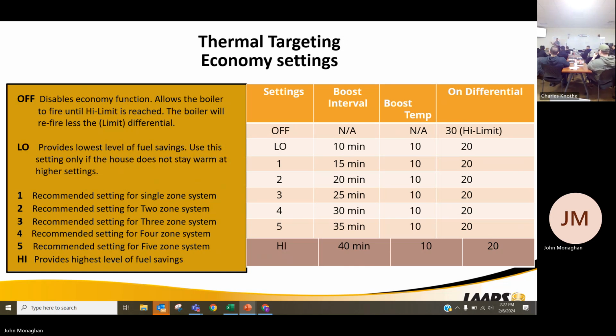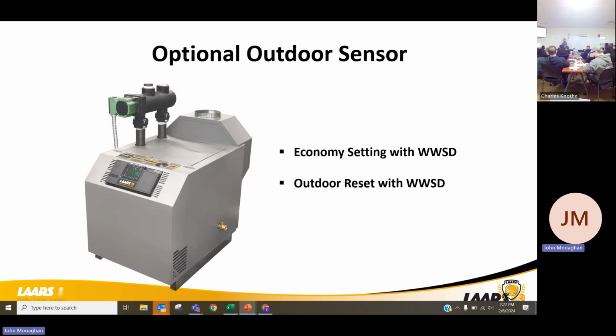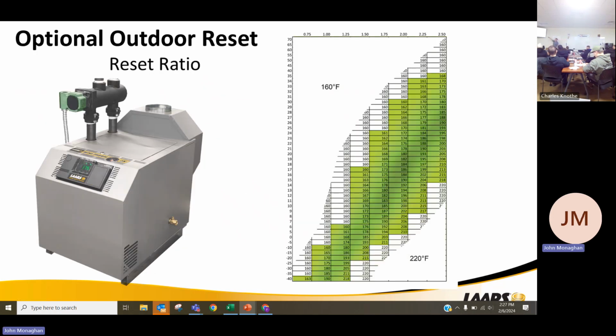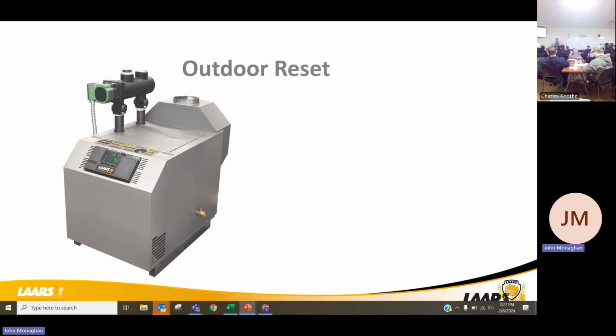And that's where the Department of Energy determined this was one of the good ones. Some of the manufacturers are using thermal purge, where the boiler will not fire until it gets below a certain temperature, or you use outdoor reset. This has the option to use either or. You put your 10K outdoor reset sensor in there, no extra control, and you can set this up for outdoor reset. We're doing our outdoor reset. We would have basically our curve. Minimum boiler water temperature is going to be 160. Max is going to be 220 degrees. And it's going to basically work off of its curve.